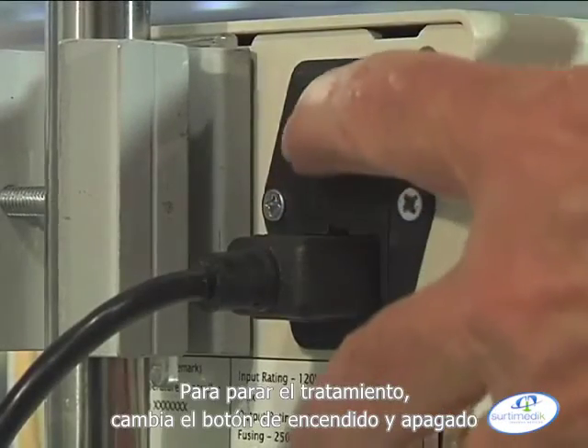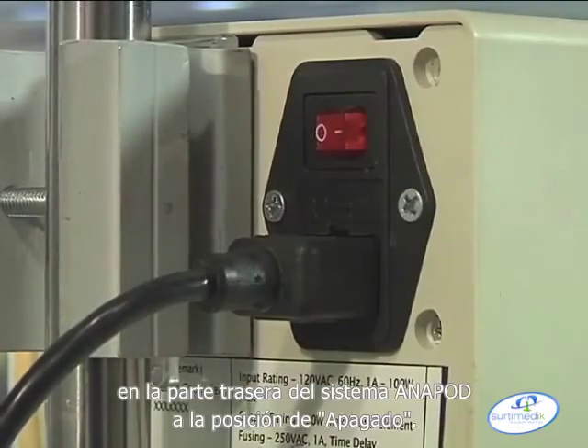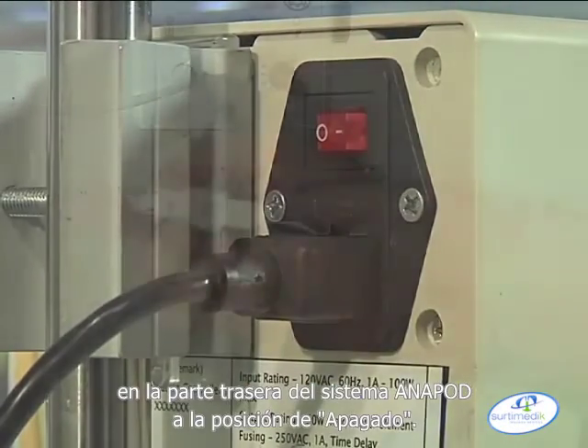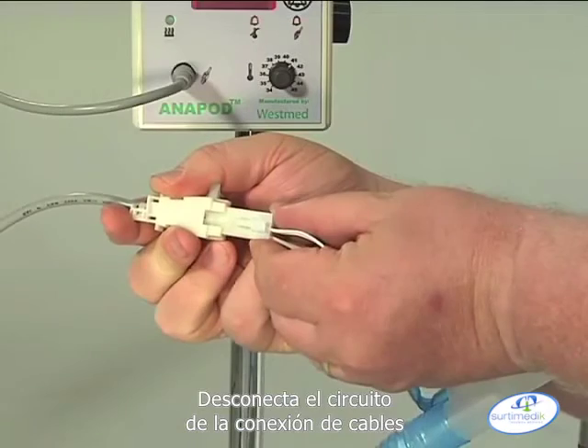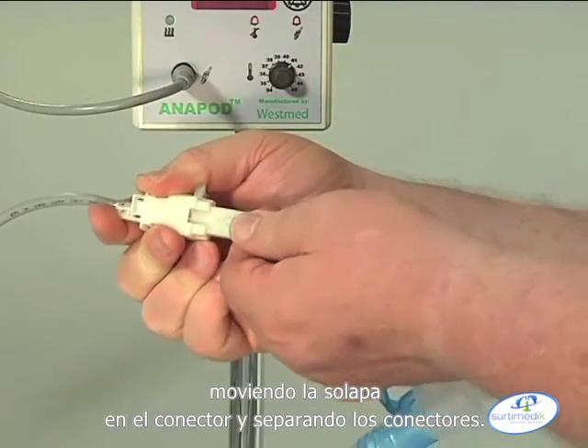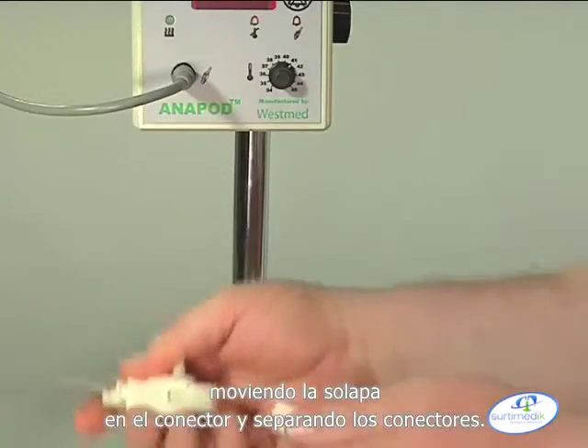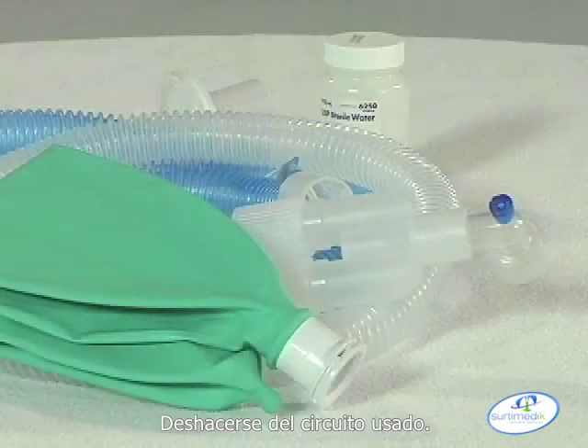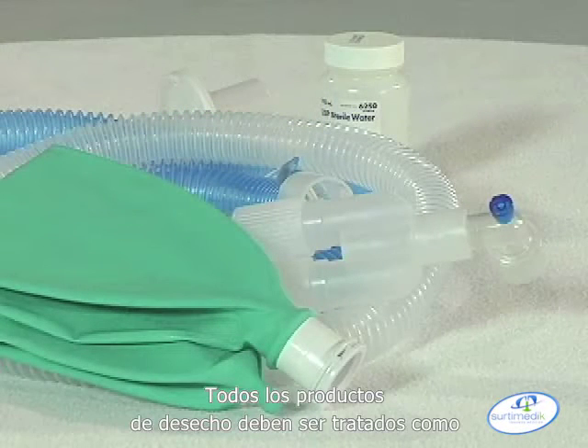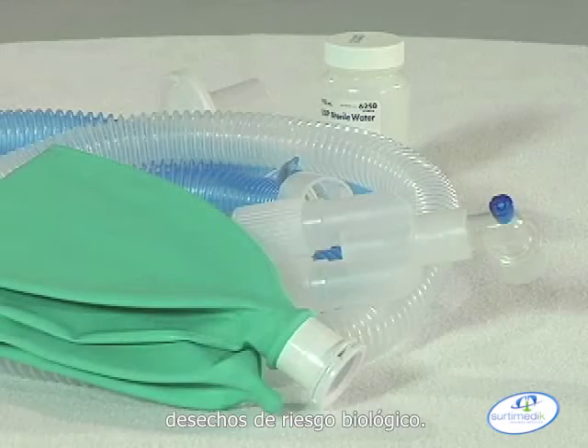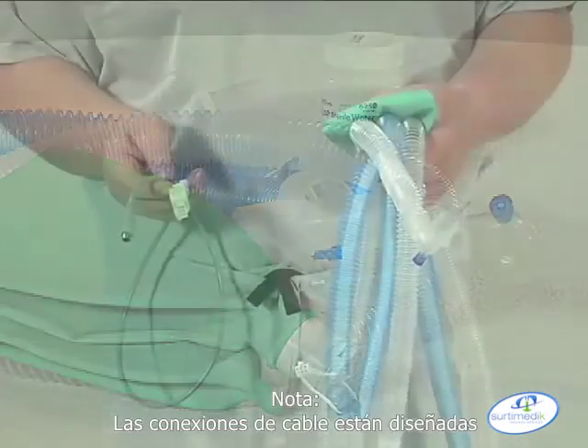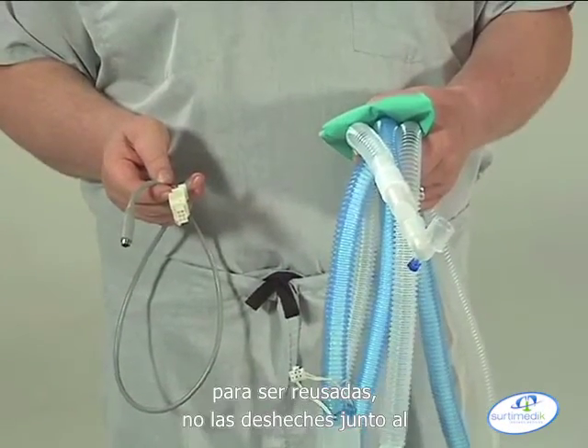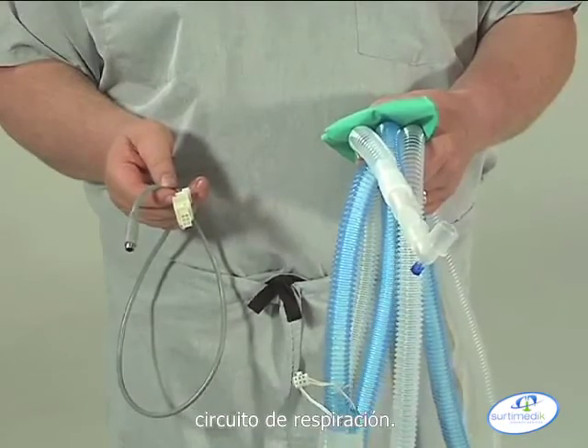To stop treatment, turn the on-off control switch on the rear of the Anapod to the off position. Disconnect the circuit from the cable assembly by depressing the latch on the white connector and separating the connectors. Dispose of the used circuit. All disposable products should be treated as biohazard waste. Note: the cable assembly is designed to be reused. Do not dispose with the breathing circuit.